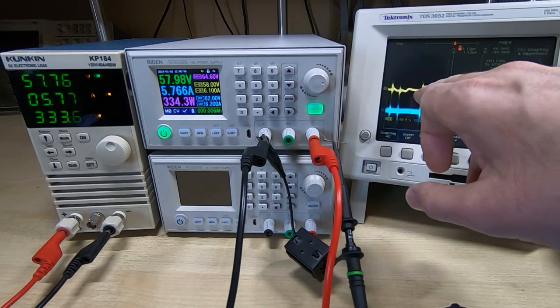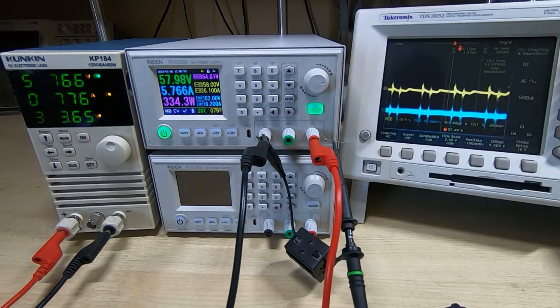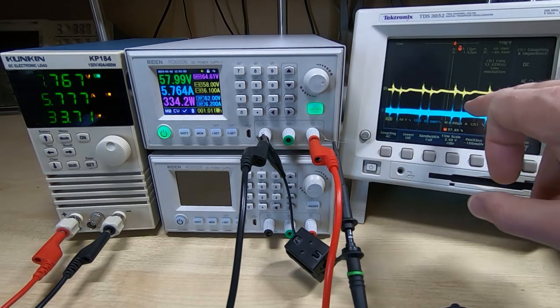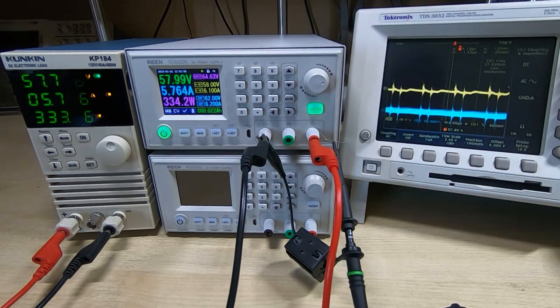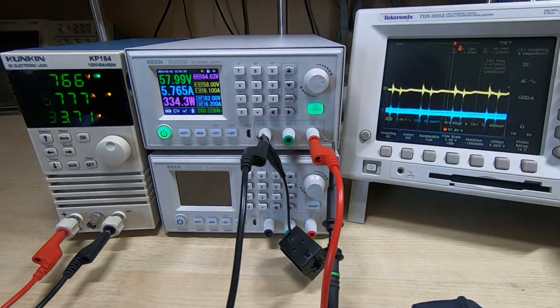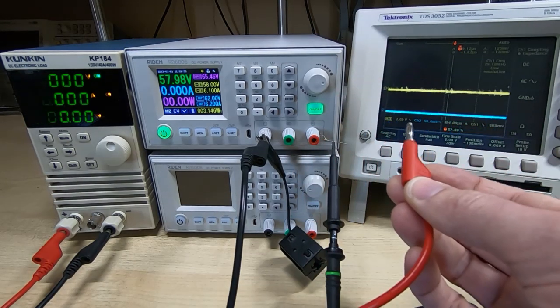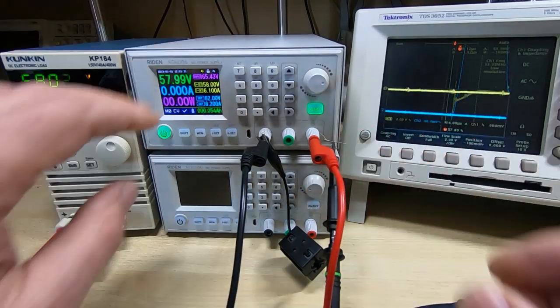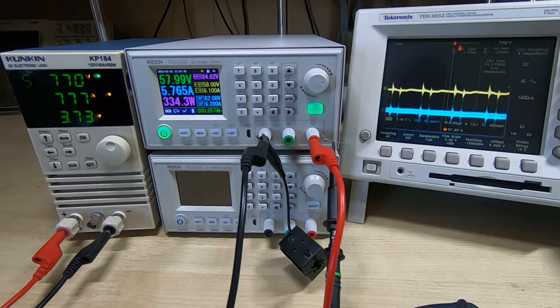So we can now see that these noise spikes have grown quite considerably. We're up to about 6 volts peak to peak, and they are directly in phase with the current we're picking up using the current clamp, which uses a different method of measurement and is more isolated from the inductive coupling we're seeing. In other words, the spikes we're seeing are real now. These are what are coming out of the Riden supply. If I disconnect the cable, you'll see that they go away. I'll reconnect it, turn the load back on, and you can see they're consistent, they're there all the time, and we're getting about 4.5, 5 volts peak to peak noise, and that is obviously quite poor.